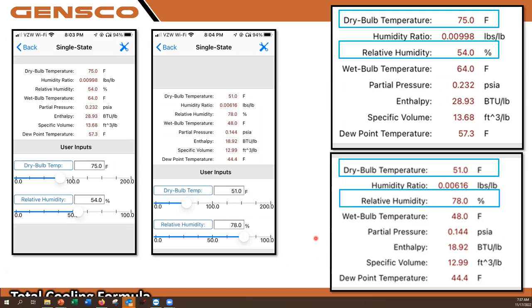I like humidity because it means something to me. I understand if I see a wet bulb number that approaches the dry bulb number, but I'd rather see the humidity percent because homeowners understand that. They don't understand what wet bulb is. You can see also where it displays the dew point temperature. In the case of this picture here at the top, our return air dew point is 57. Why is that handy? That's the temperature at which something in the room, like a glass of iced tea, that's below 57 starts building condensation on the outside of the glass.